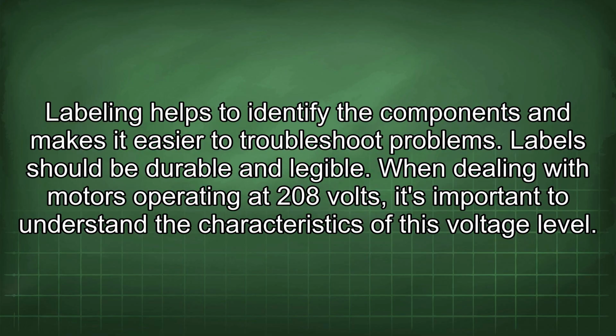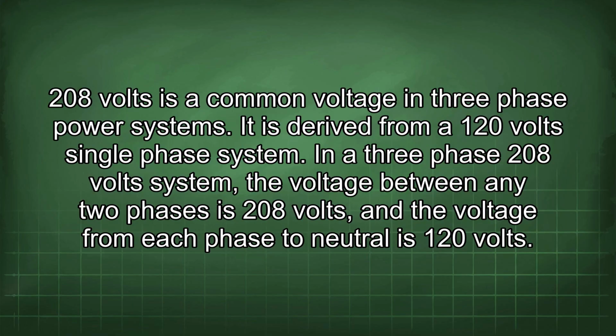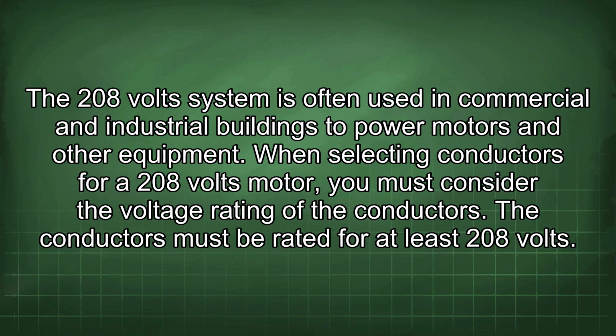When dealing with motors operating at 208 volts, it's important to understand the characteristics of this voltage level. 208 volts is a common voltage in three-phase power systems. It is derived from a 120 volt single-phase system. In a three-phase 208 volt system, the voltage between any two phases is 208 volts, and the voltage from each phase to neutral is 120 volts. The 208 volt system is often used in commercial and industrial buildings to power motors and other equipment.